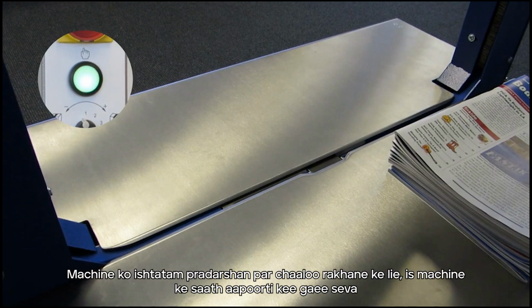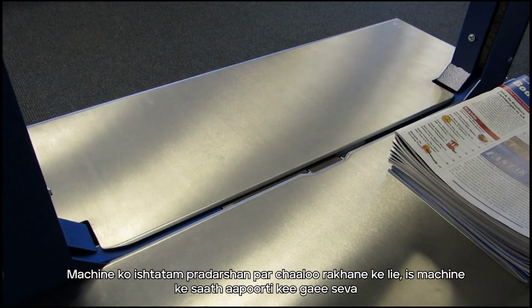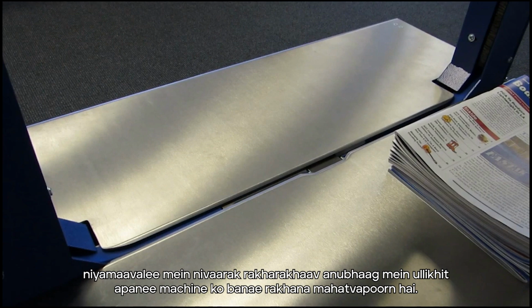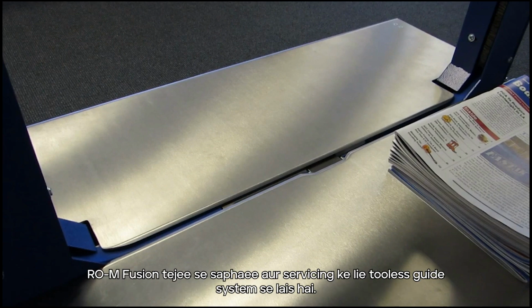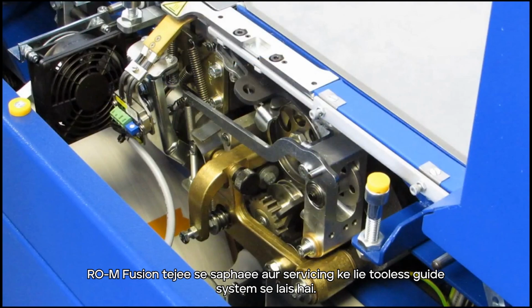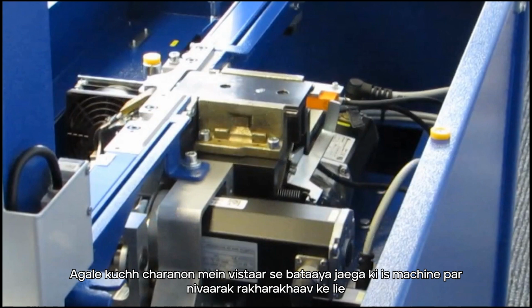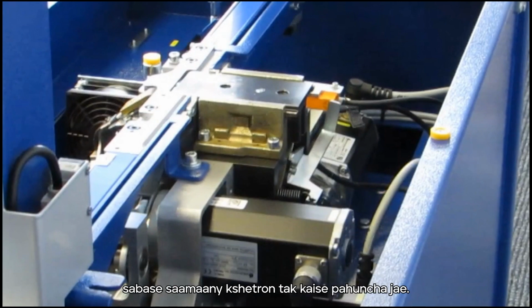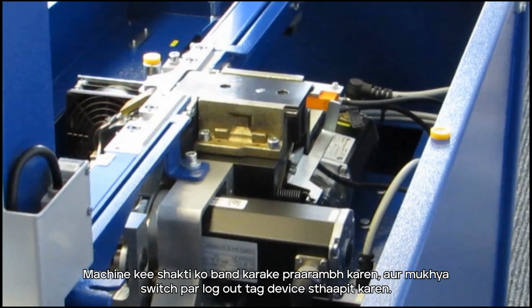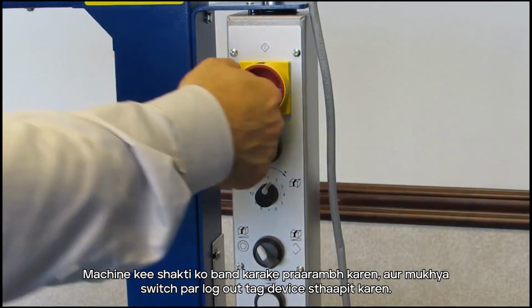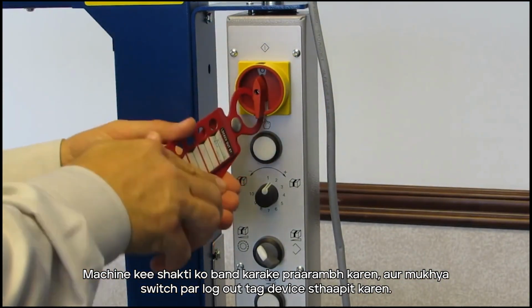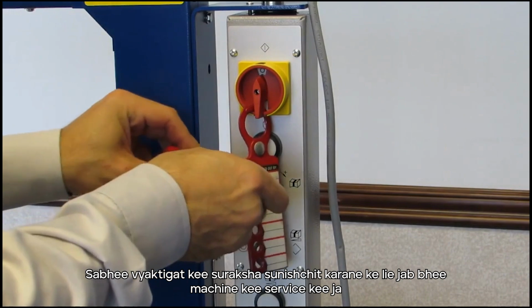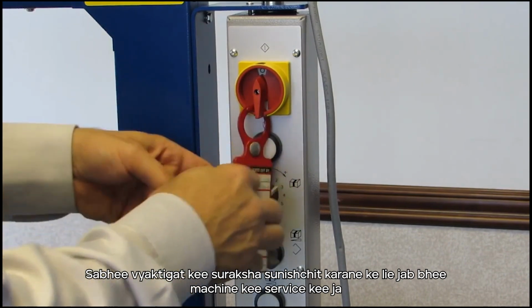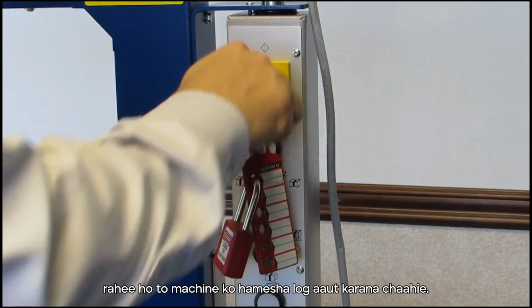To keep the machine running at optimum performance, it is important to maintain your machine as outlined in the preventive maintenance section in the service manual supplied with this machine. The ROM Fusion is equipped with a toolless guide system for fast cleaning and servicing. The next few steps will detail how to access the most common areas for preventive maintenance on this machine. Start by shutting the machine power off and install a lockout-tagout device to the main power switch. The machine should always be locked out whenever it is being serviced to ensure the safety of all personnel.